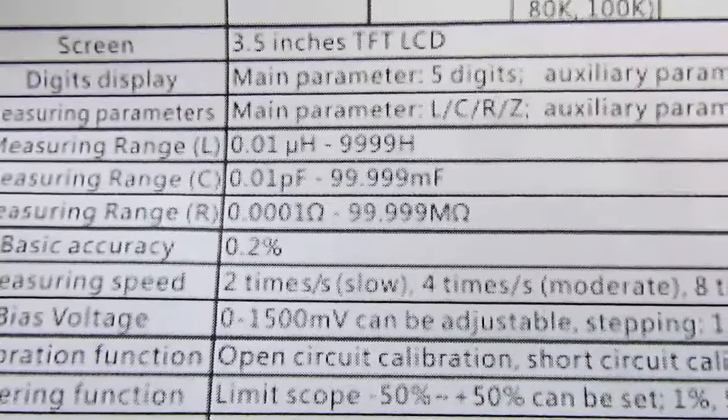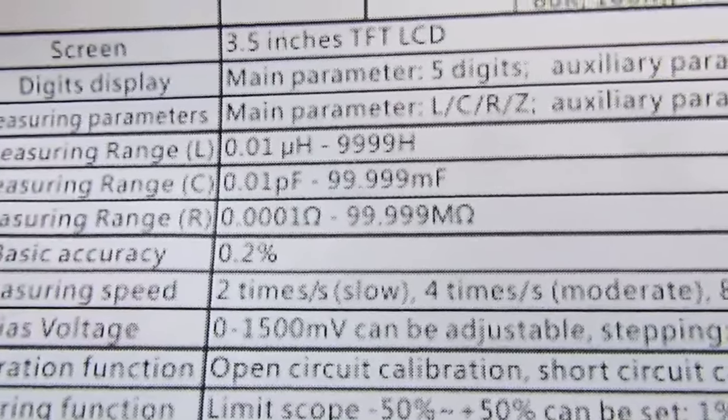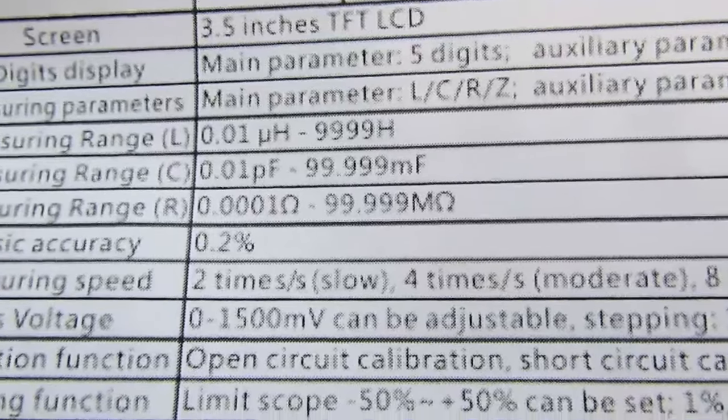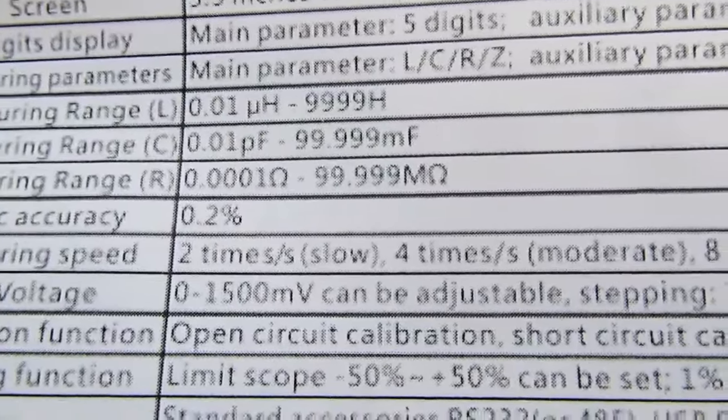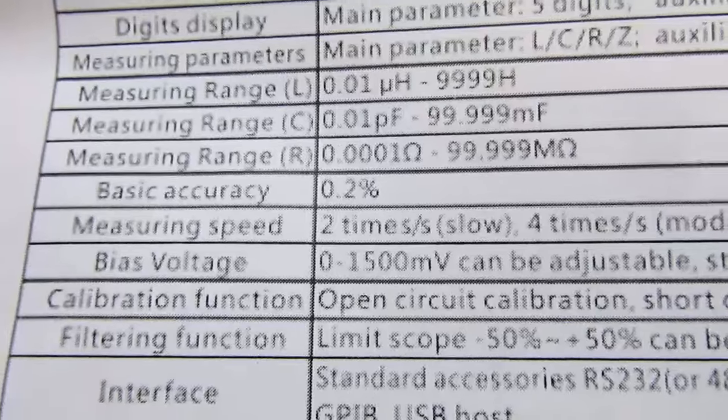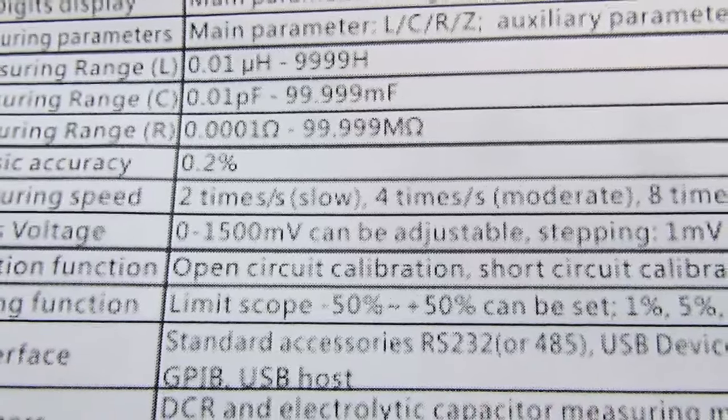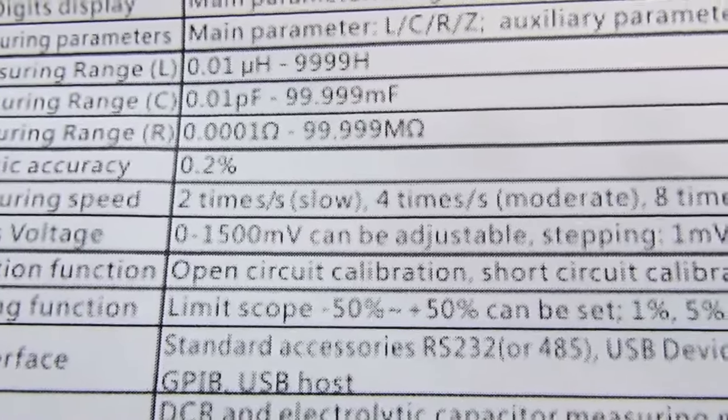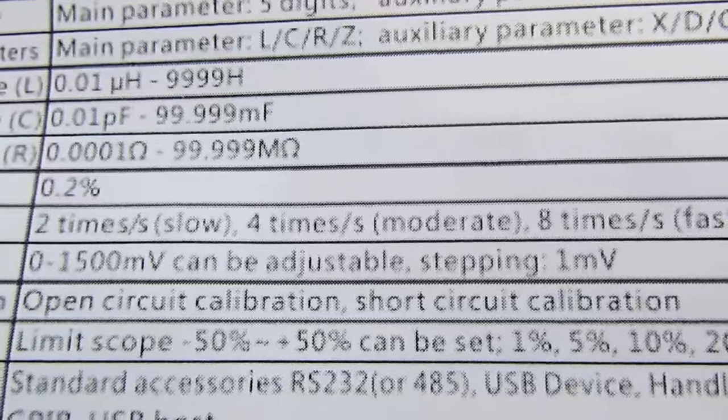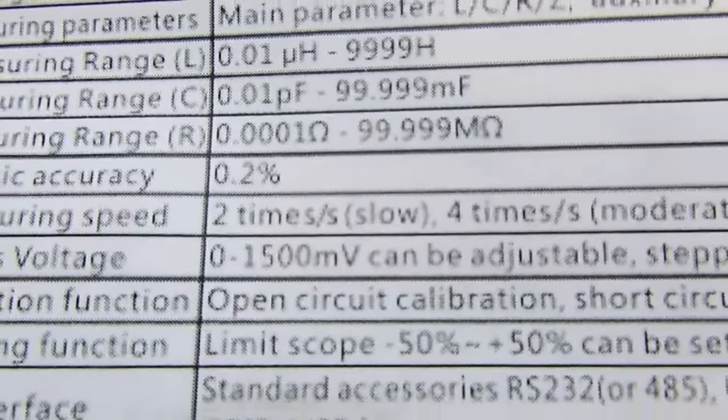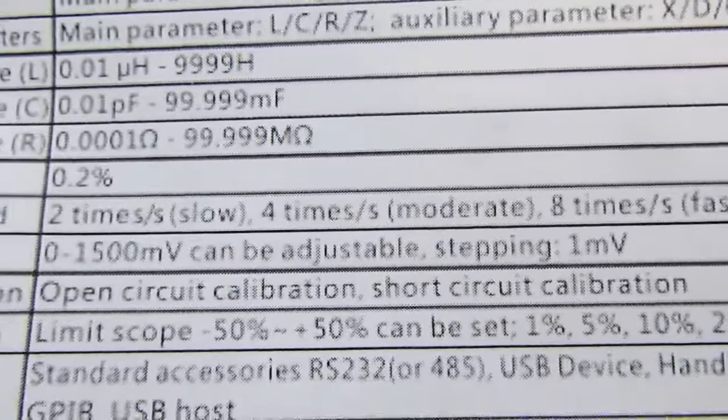Measuring range: 0.01 microhenries to 9999 henries, 0.01 picofarads to 99.999 millifarads, and 0.0001 ohms to 99.999 megaohms. Basic accuracy: 0.2%. Measuring speed: 2 times per second, 4 times per second, or 8 times per second - slow, medium, and fast.